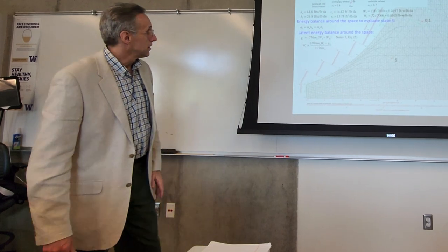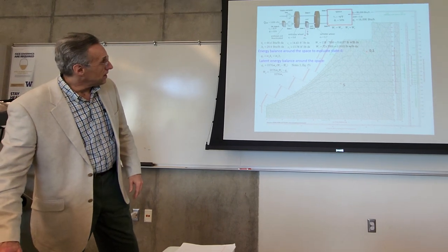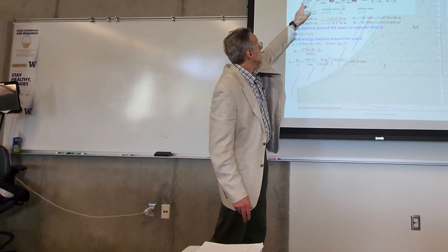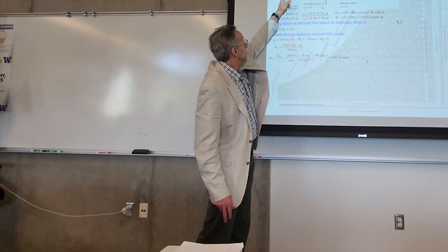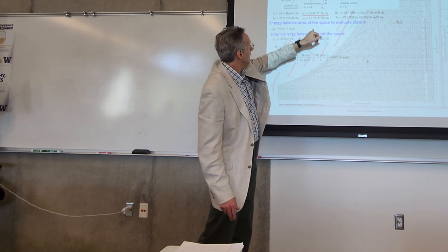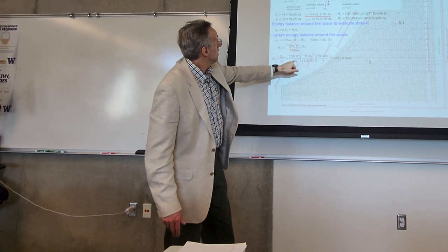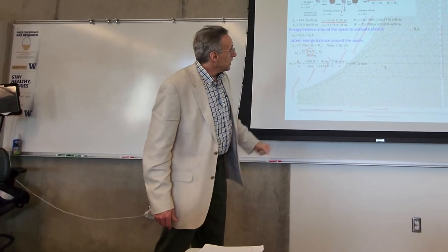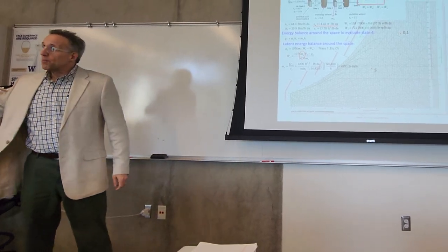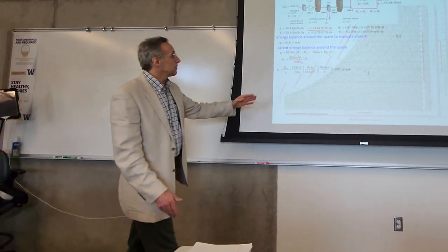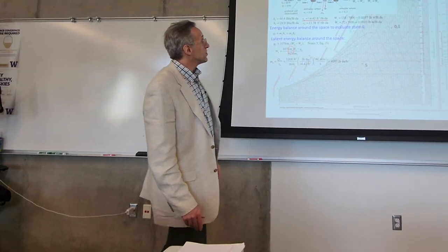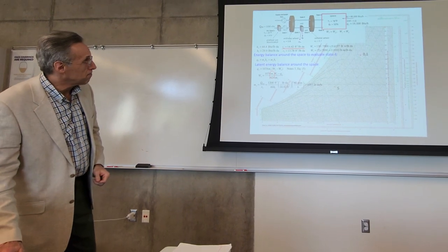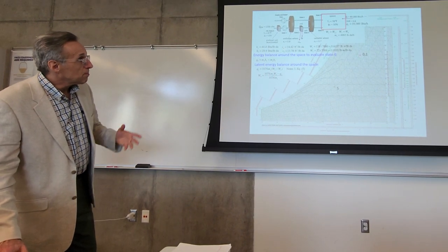And we just need to figure out now what the mass flow rate of the air is, and we can get that from our incoming volume flow rate and the specific volume at the incoming state, which is 14.42. So our mass flow rate is 4993 pounds of dry air per hour, and that's the same all the way through because we're just running the same air all the way through the system, changing the moisture in different places, but the dry air component is the same. So there's our mass flow rate of dry air.